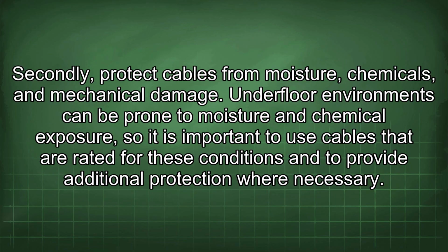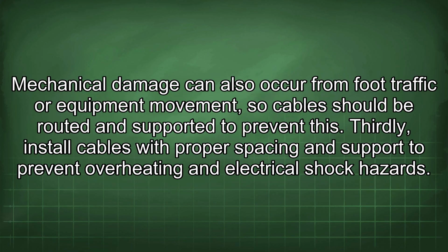Secondly, protect cables from moisture, chemicals, and mechanical damage. Underfloor environments can be prone to moisture and chemical exposure, so it is important to use cables that are rated for these conditions and to provide additional protection where necessary. Mechanical damage can also occur from foot traffic or equipment movement, so cables should be routed and supported to prevent this. Thirdly, install cables with proper spacing and support to prevent overheating and electrical shock hazards.